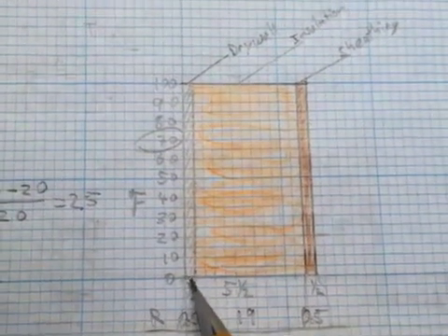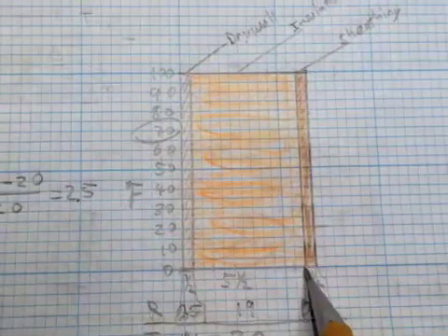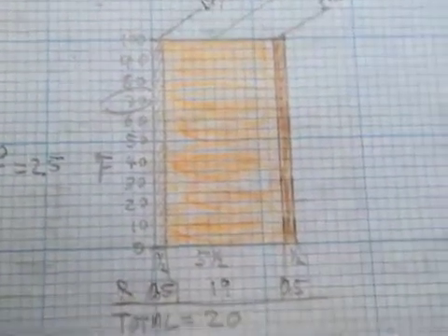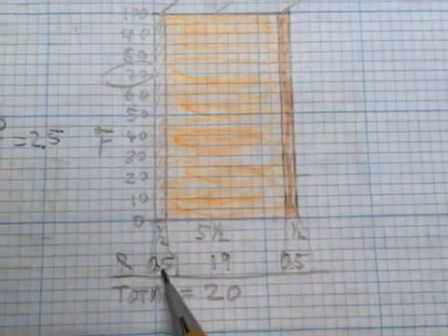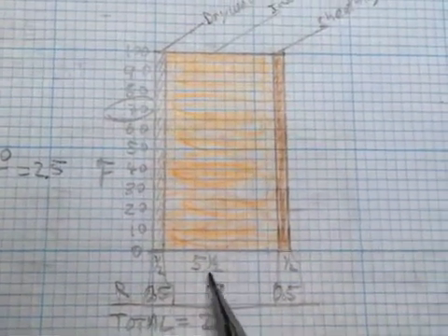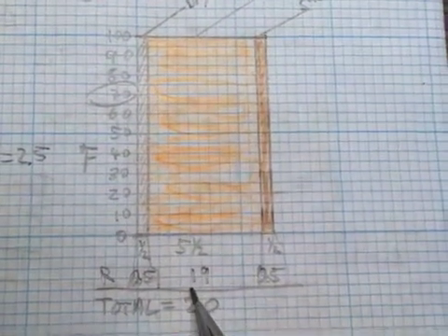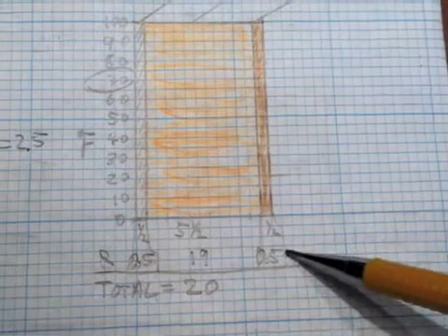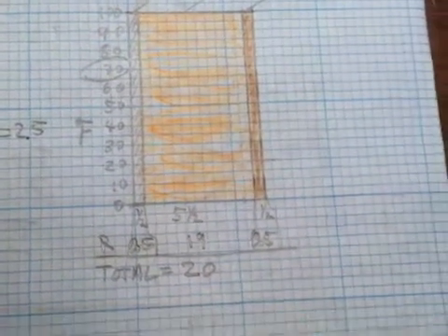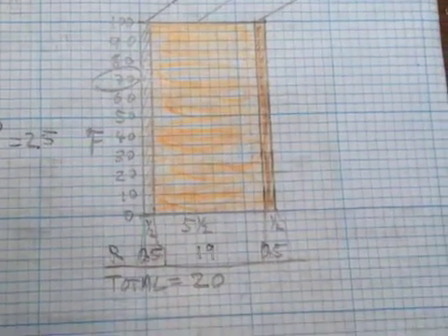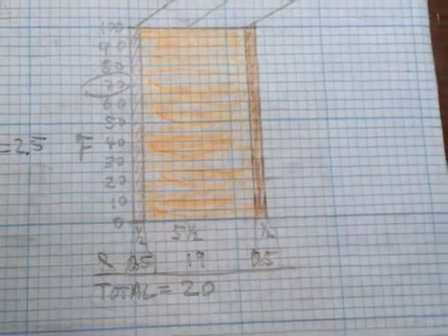This profile is drawn proportional to thickness: a half inch of drywall, five and a half inches of insulation cavity, and a half inch of sheathing on the outside. We can also describe it in terms of R-values. The drywall has an R-value of about 0.5, the insulation has an R-value of about 19, and the sheathing has an R-value of about 0.5. The total is 0.5 + 19 + 0.5 = 20, so it's R-20 through this wall.